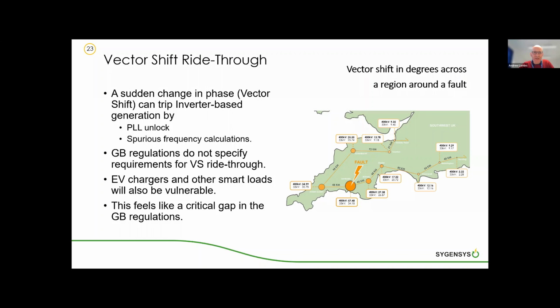EV chargers and other smart loads also rely on phase-locked loops, so they will also be vulnerable to vector shift tripping. And the lack of any ride-through requirement does feel like a critical gap in GB regulations. This map here shows the vector shift around the southwest part of the GB grid for a three-phase fault in the southwest here. Locally, you have phase jumps of almost 60 degrees, and as these propagate around the network, they reduce, but they can still be fairly substantial, 25-degree phase shift at this point here.